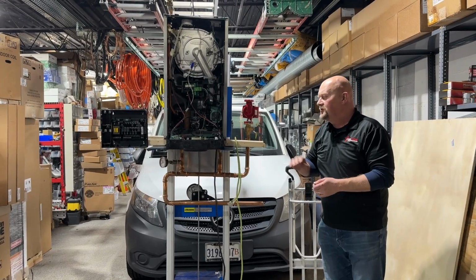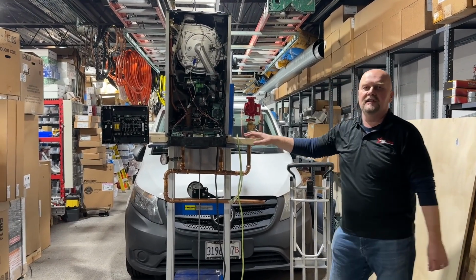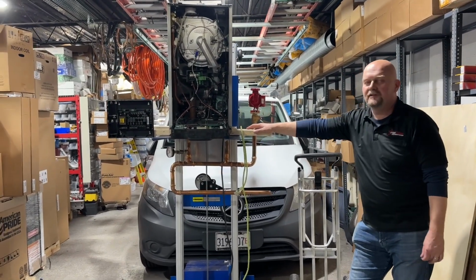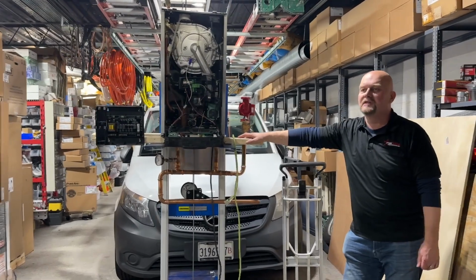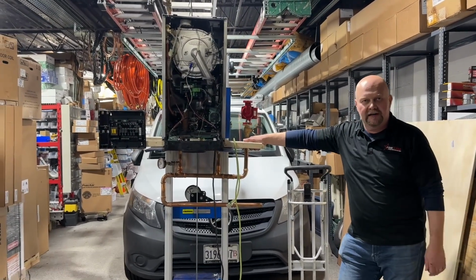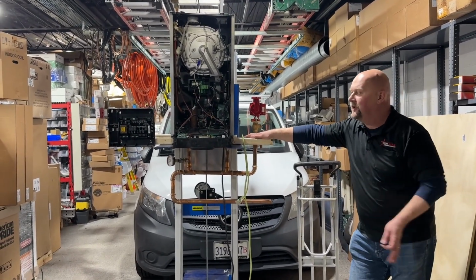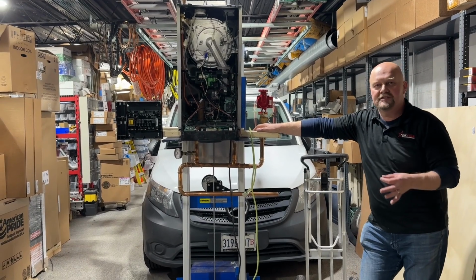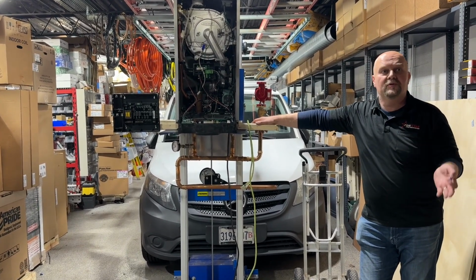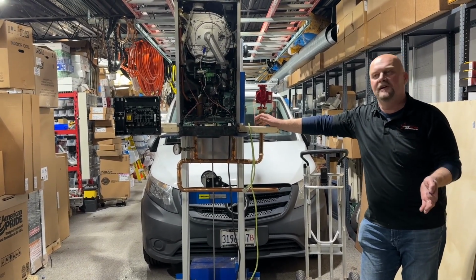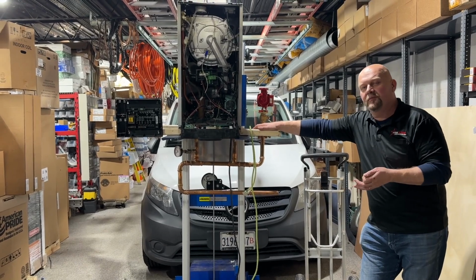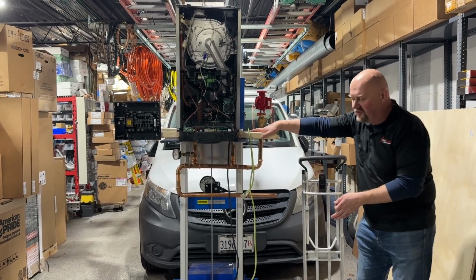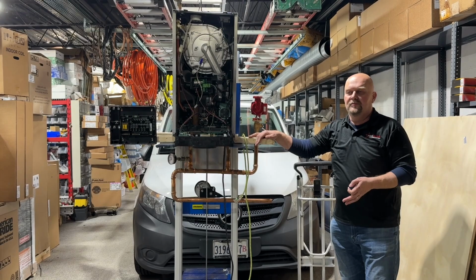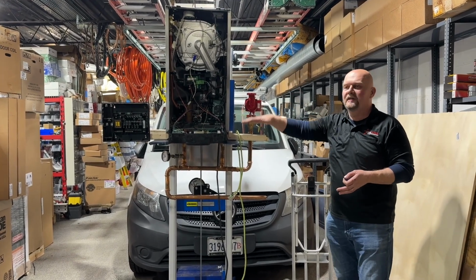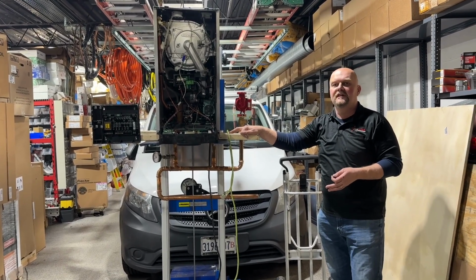Also, the reason you do want to have it on the supply side is this tank is meant to counter pressure increases, and the supply pipe is hotter. It's post the boiler, so it'll react faster to a pressure change. You all know pressure and temperature are directly related. When the temperature starts going up in the boiler, so does the pressure, and this is here to literally counter that, because the pressure in your system remains the same until you start heating up the water.